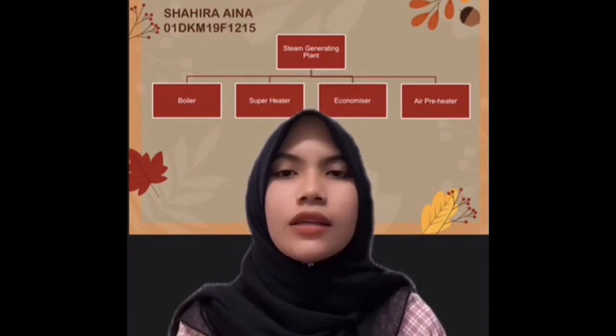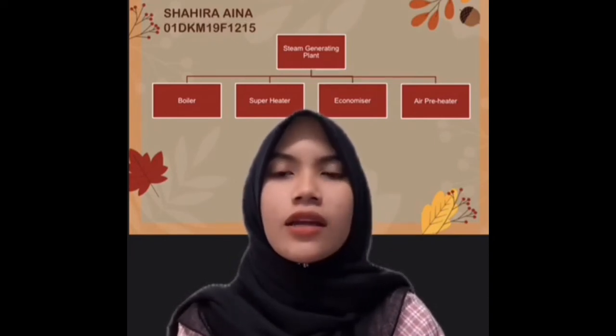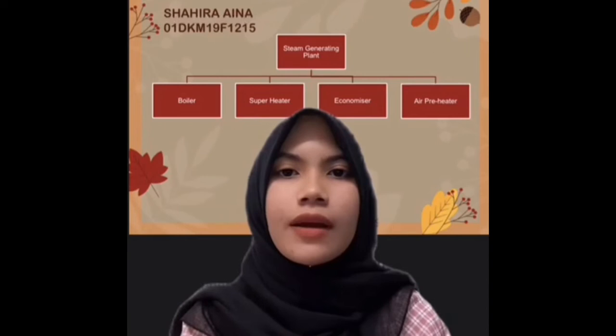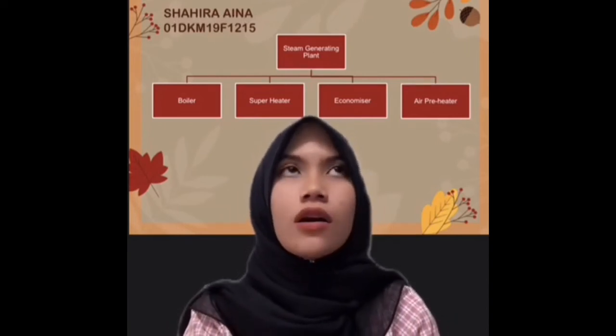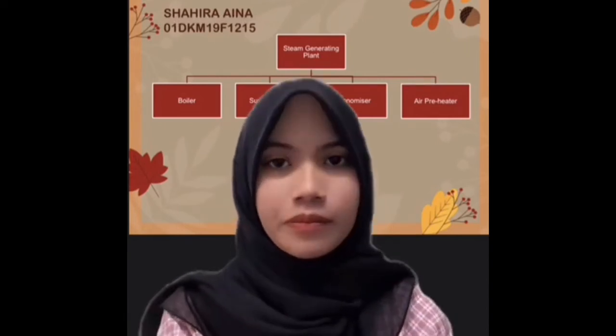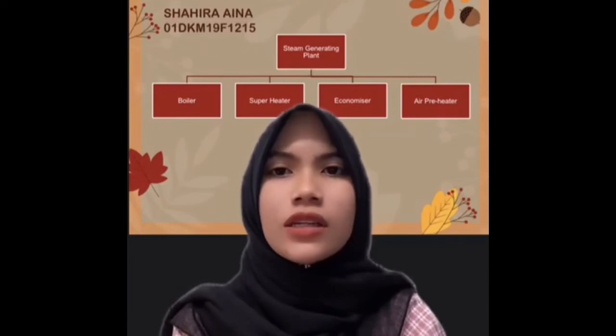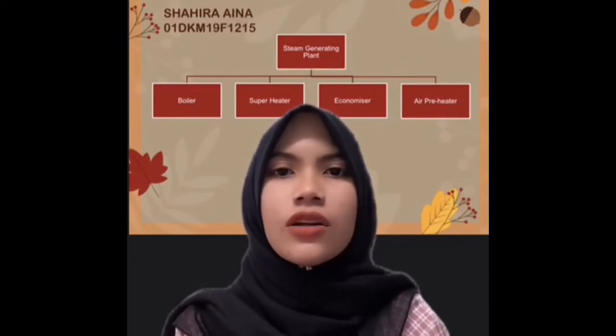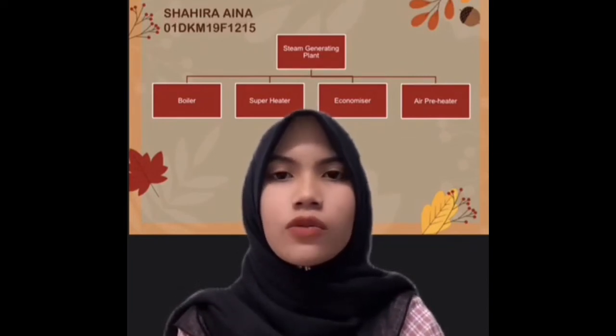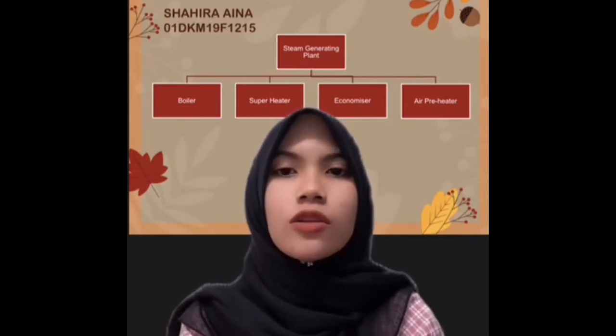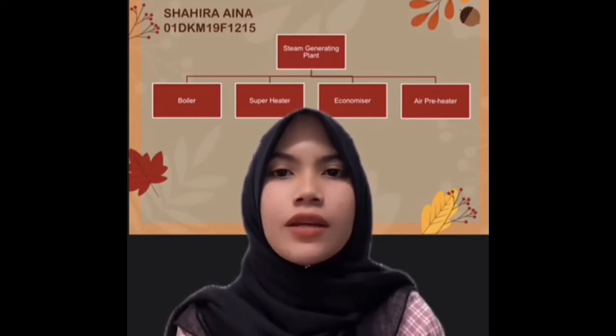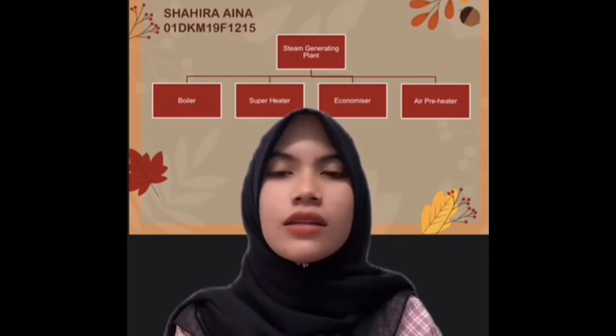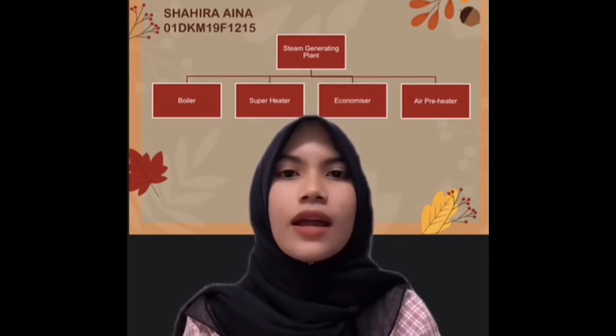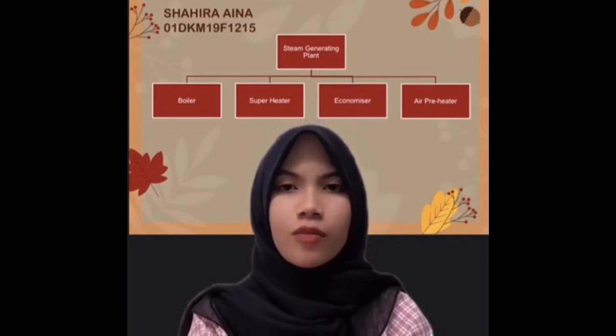A preheater. An air preheater increases the temperature of the air supply for coal burning by deriving heat from flue gas. Air is drawn from the atmosphere by a forced draft fan and passed through a preheater before supplying to the boiler furnace. The preheater extracts heat from the flue gas and increases the temperature of air used for the coal combustion.